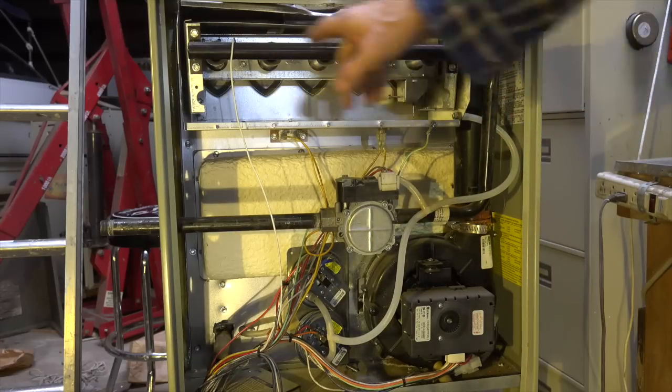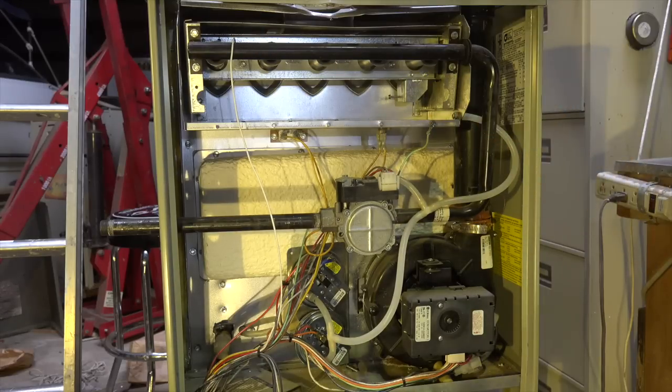I'm going to take this manifold off and the burners out and let's look inside there and see if we can actually see that crack. Now of course this isn't as perfect as it could be trying to put a camera in there, but you can't see any sign of that crack using a flashlight once we've pulled the burners out.